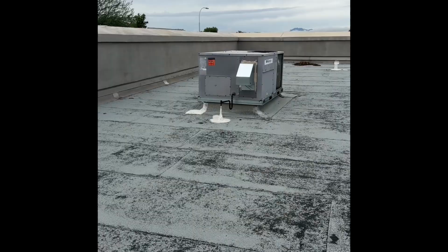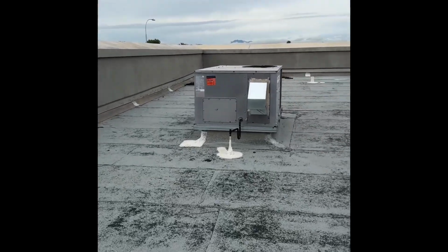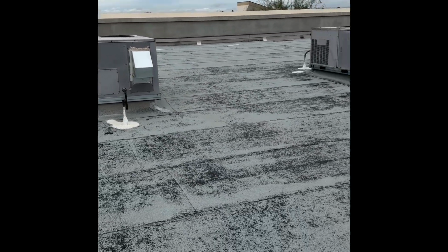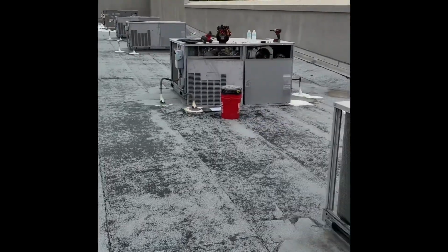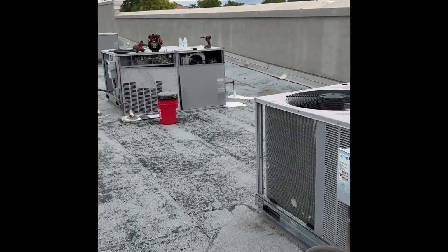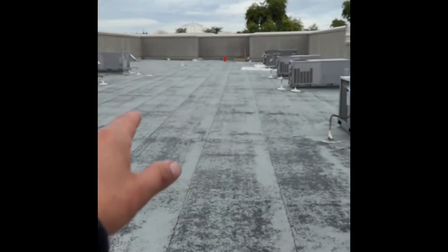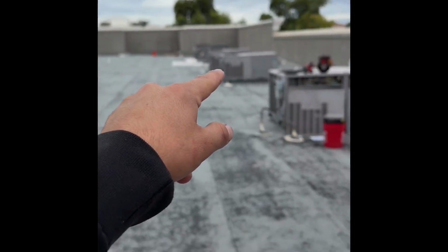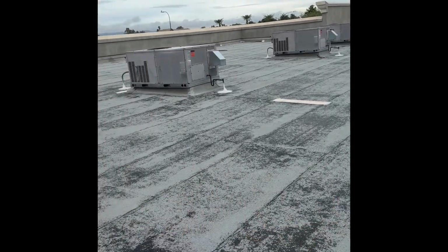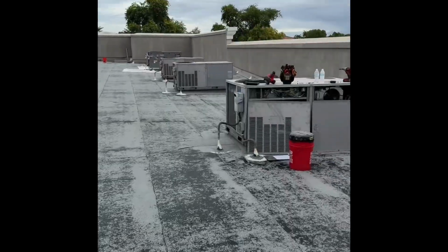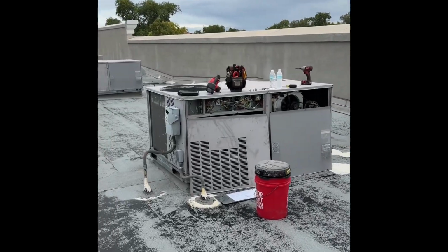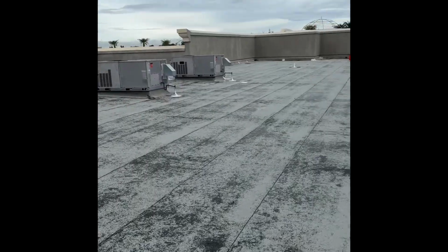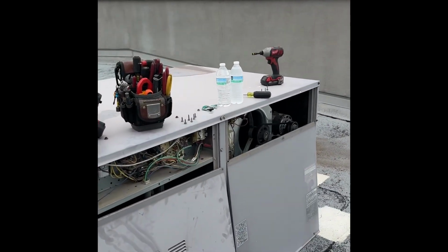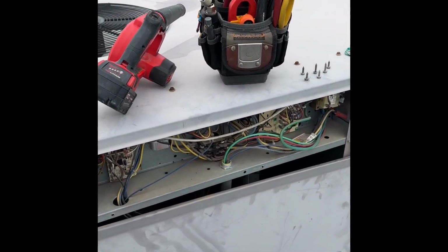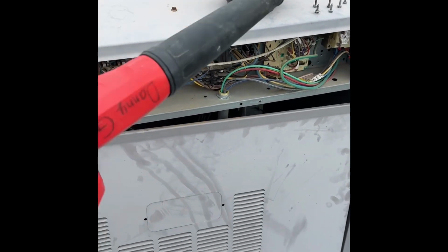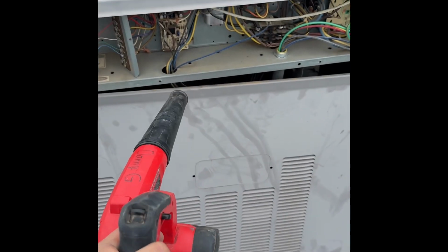Okay, so this is where we're at for today. We have 8 Carrier package units, 5-ton heat pumps. I already did filters. I already washed coils for all 8 of them, starting from those 2 in the front, working our way back here to there. So yeah, if you're new in the trade, commercial HVAC, you're gonna be at places like this doing stuff like this, especially in the winter where you just do inspection PMs, right? People use brushes. I use a blower, dust the electrical cabinets.